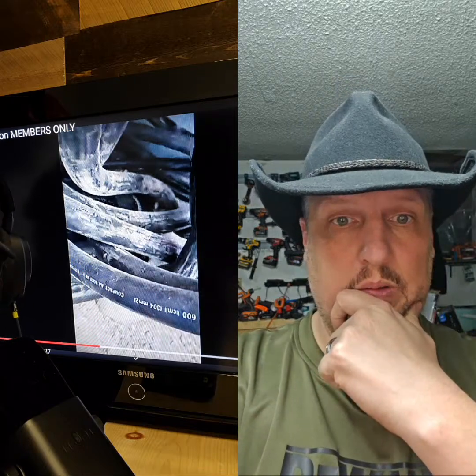At work, we had a 480 volt heater that malfunctioned. It didn't trip the 20 amp bucket, but it did trip the MCC main. Why would this happen? Perfect. These are the questions that I live for. Didn't loop back to the breaker, is my guess.